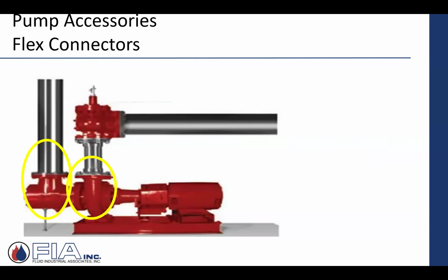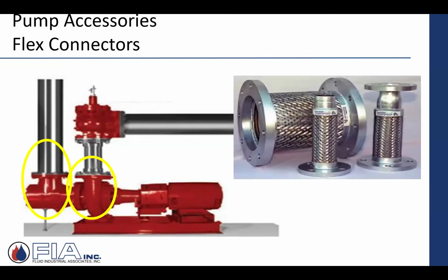And then the last thing, just for a couple of accessories, is going to be these flex connectors. And the flex connectors, typically it might be just last minute alignment, taking that system piping that's coming back and aligning it to, in this case here, maybe the suction diffuser, and then on this side the discharge tying in.